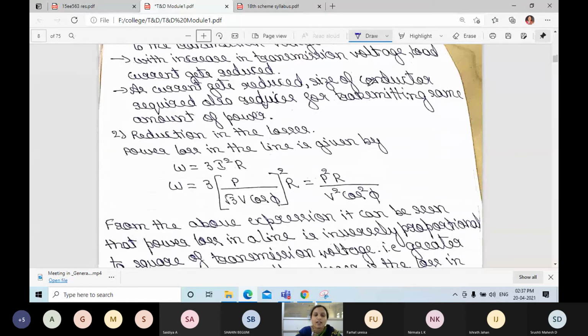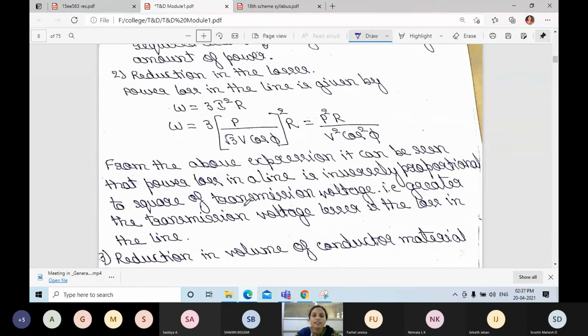Next, reduction in the losses. Power loss in the line is given by W is equal to 3 I square R. Substituting I as P divided by square root of 3 into V into cos phi, into R. Here also you can observe it is inversely proportional. As you increase the voltage level, the losses are reduced. The power loss in a line is inversely proportional to the square of the transmission voltage, so the greater the transmission voltage, the lesser the loss in the line. This is the second advantage.